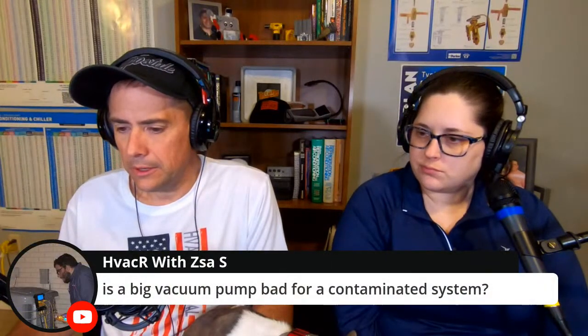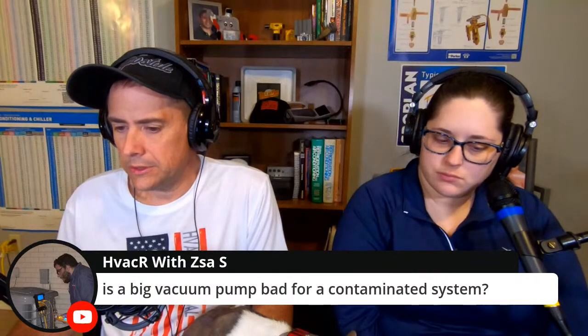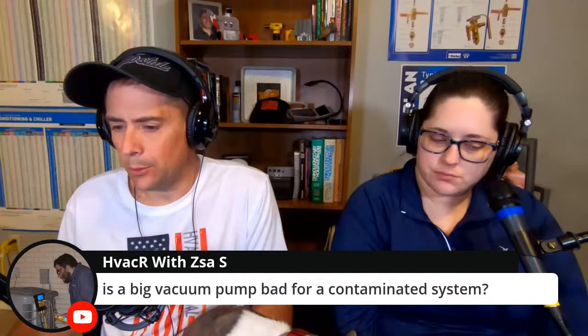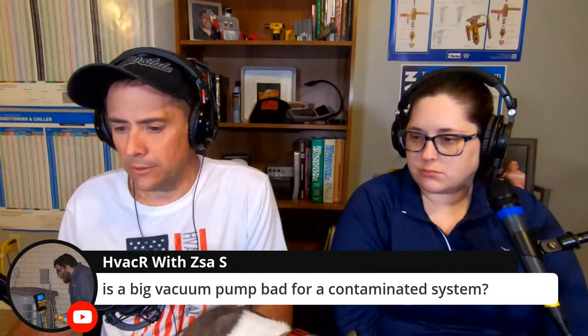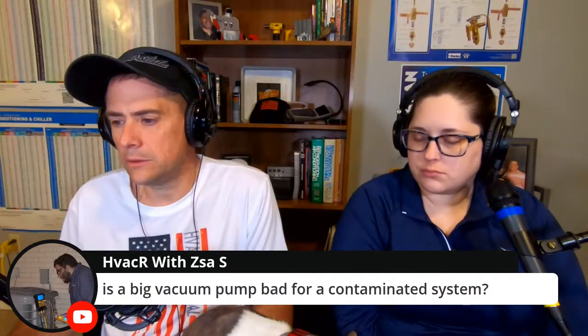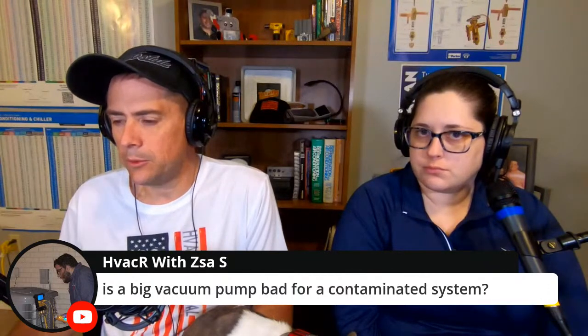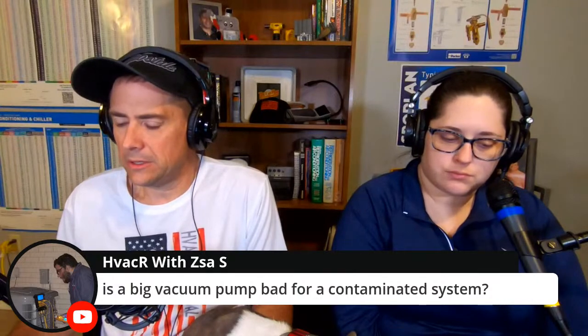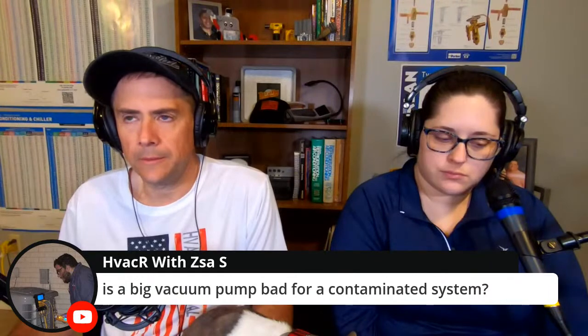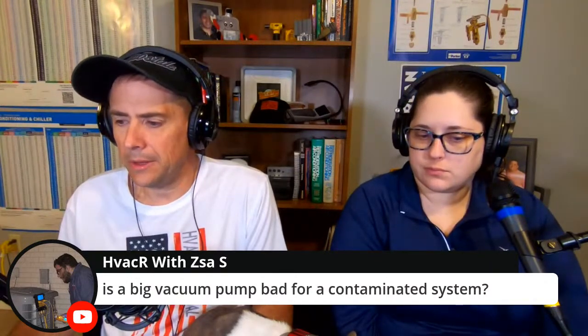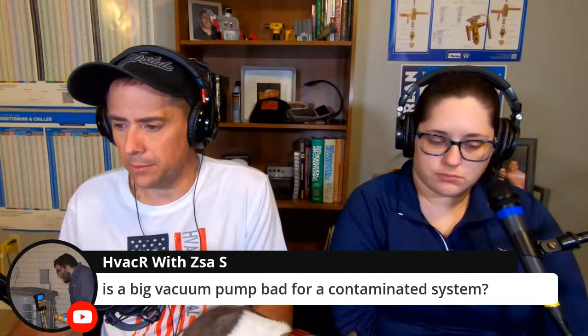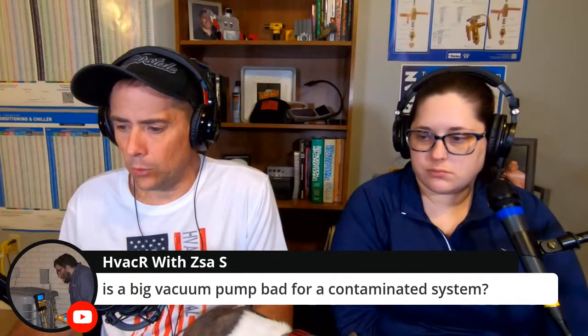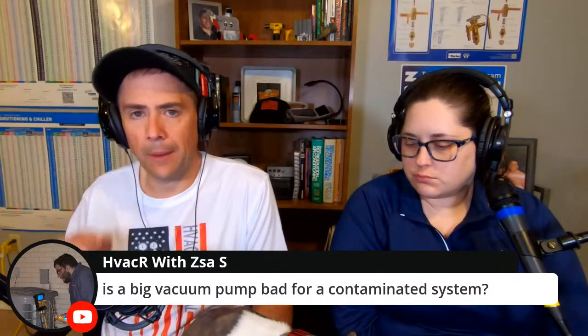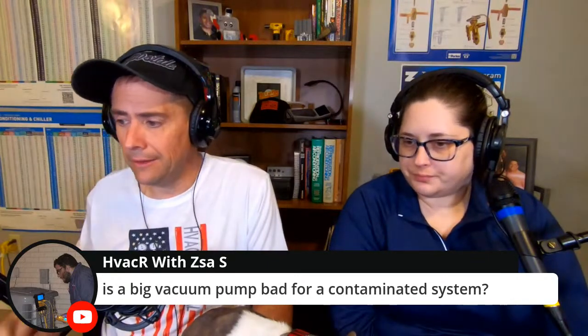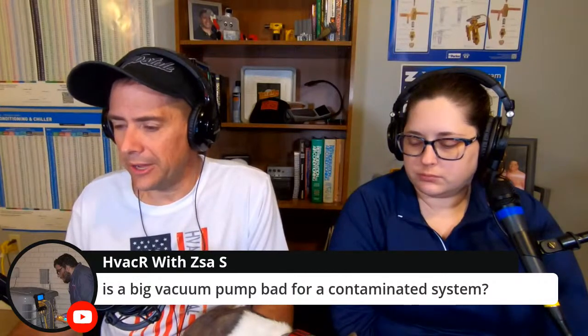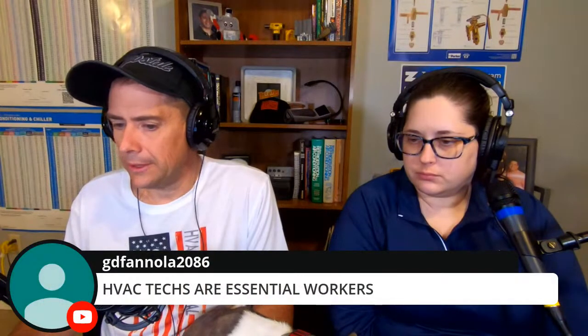Is a big vacuum pump bad for contaminated systems? Are we talking moisture and stuff? My feeling is the authority on vacuum pumps is Jim Bergman, that's where I've learned most of my vacuum knowledge from. He's got videos on whether you can really freeze the moisture in the system if you're pulling down too quickly, and other things like that. Myself, my Fieldpiece vacuum pump is 8 CFM, and my JB is a 6, and I've never noticed anything bad. Most of your cleanup is going to be done with your filter dryers and proper refrigeration practices. So I'm not as worried about vacuum size, especially when doing an evaporator startup on a new system. I'm pulling them down to 80 microns, stuff like that, which is nuts, and you're doing it sometimes in less than 10 minutes. It's nuts, but yeah, we are essential.